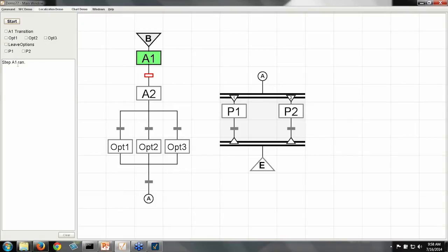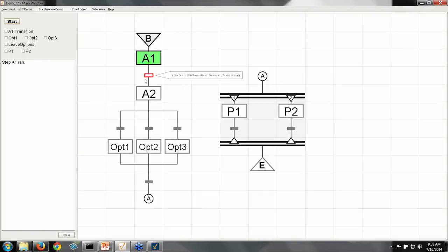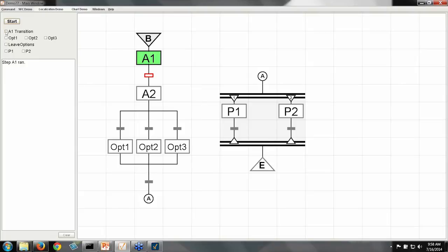And here I've run my first step, A1, which gives me this little message that my step ran. And now my chart is waiting, and it's sitting here at this transition because this condition is false. And it's waiting for me to make a tag become true, which is this A1 transition tag. So as soon as I make this tag true, the chart will move on past A1 and go to A2, like so.